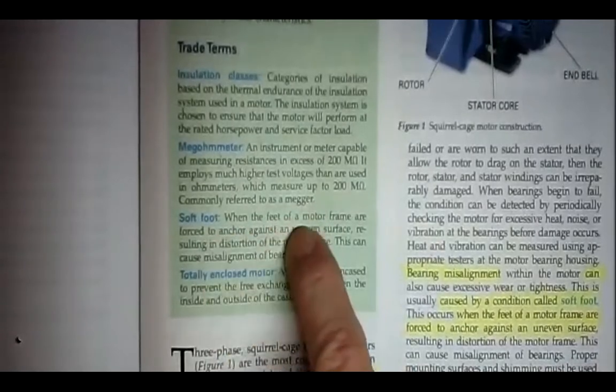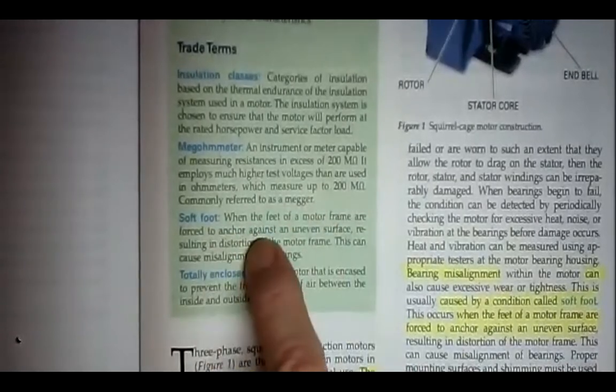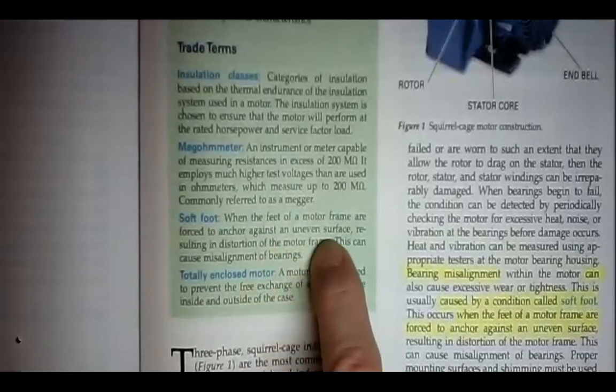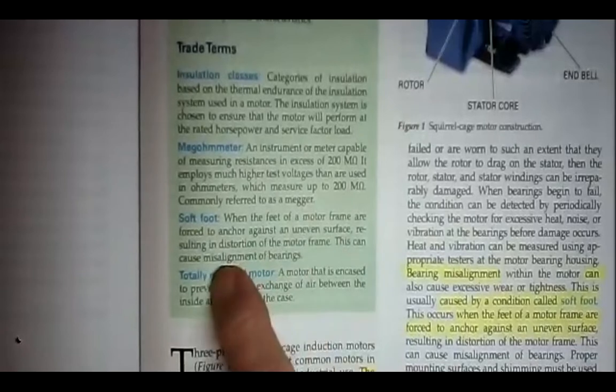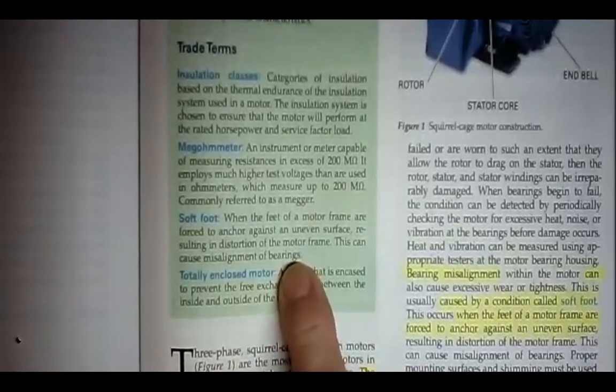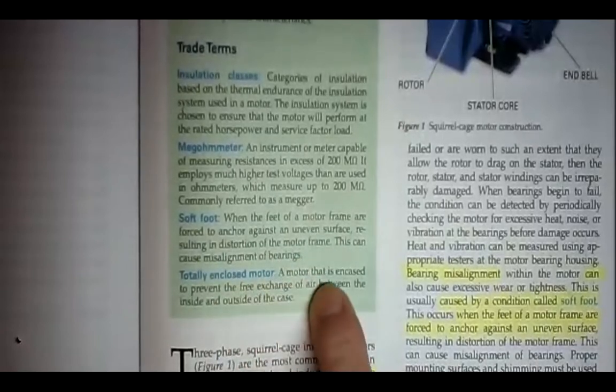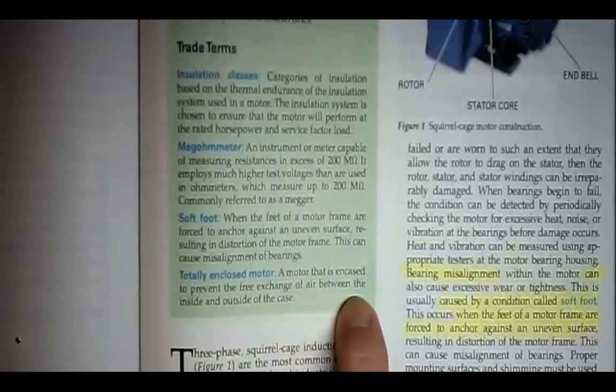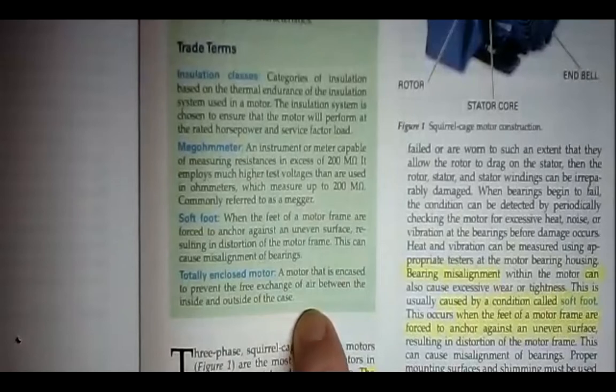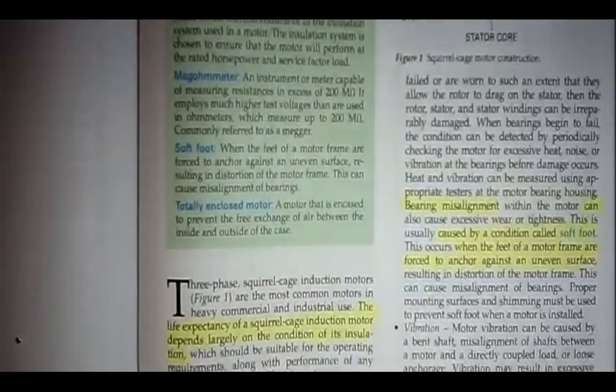Soft footing. When the feet of a motor frame are forced to anchor against an uneven surface resulting in distortion of the motor frame, this can cause misalignment of the bearings. Totally enclosed motor is a motor that is encased to prevent the free exchange of air between the inside and outside of the case. Sometimes they call it hermetically sealed.